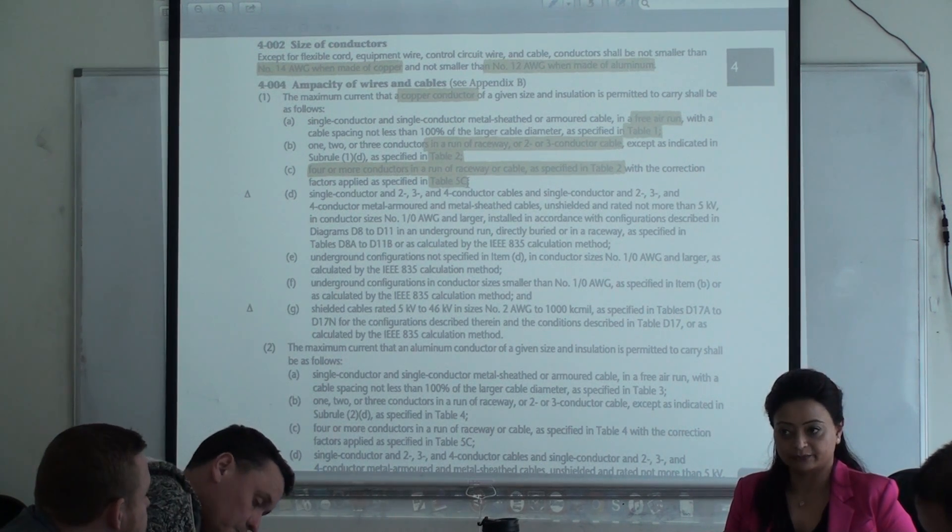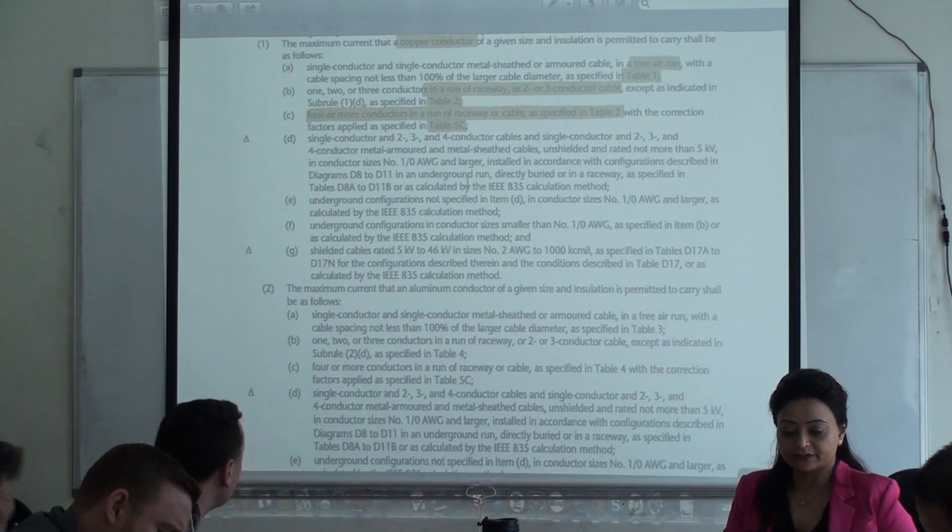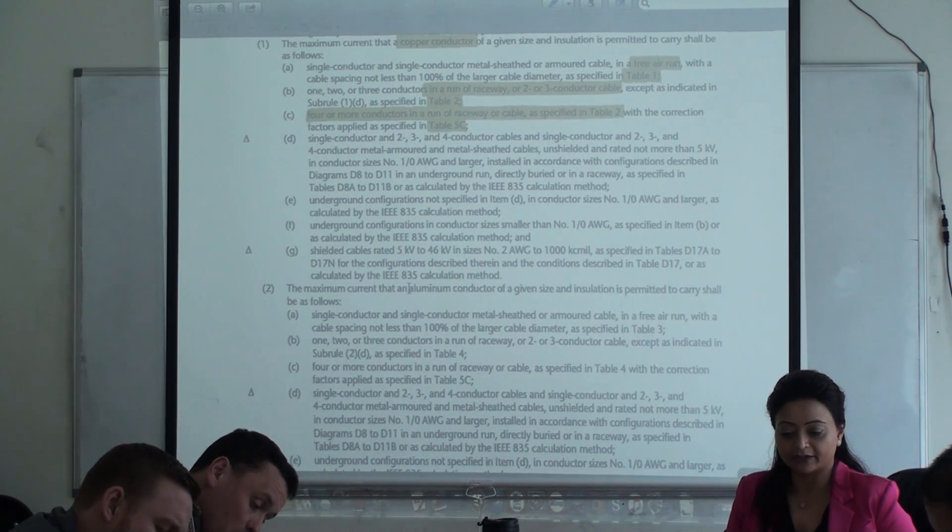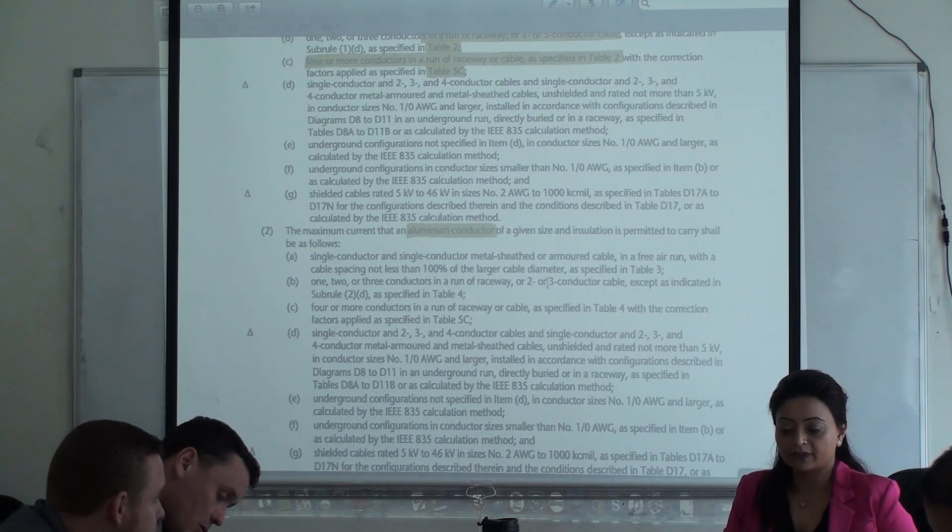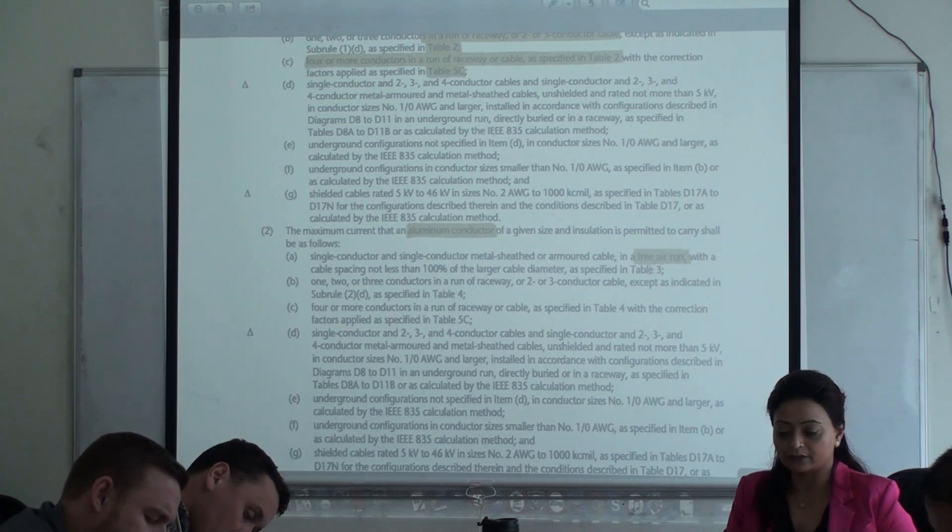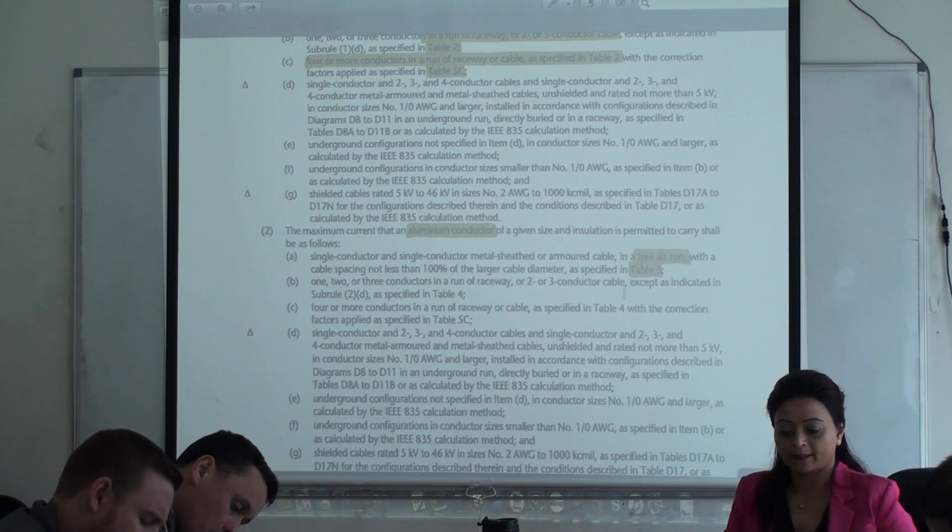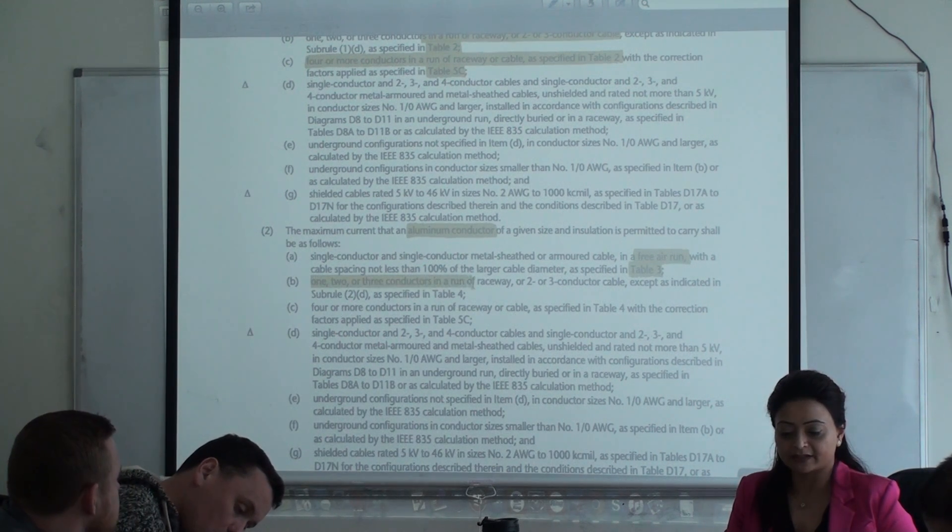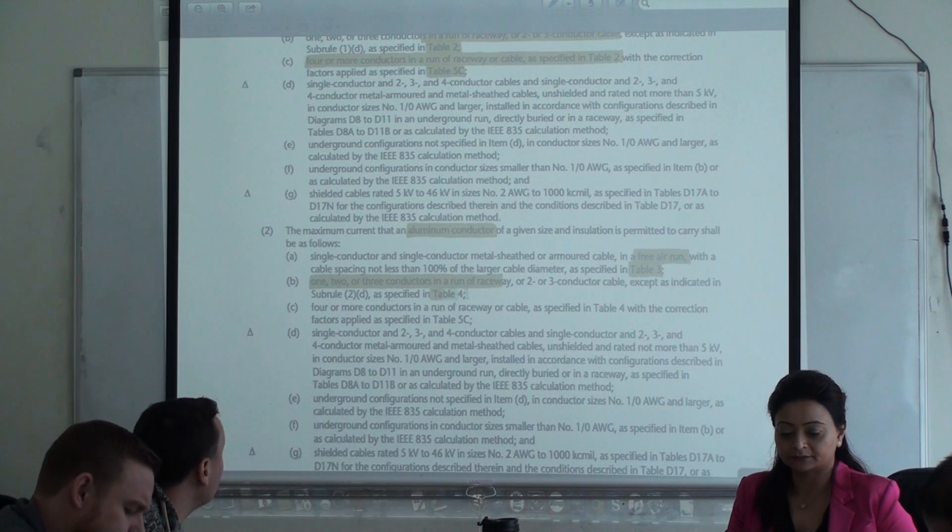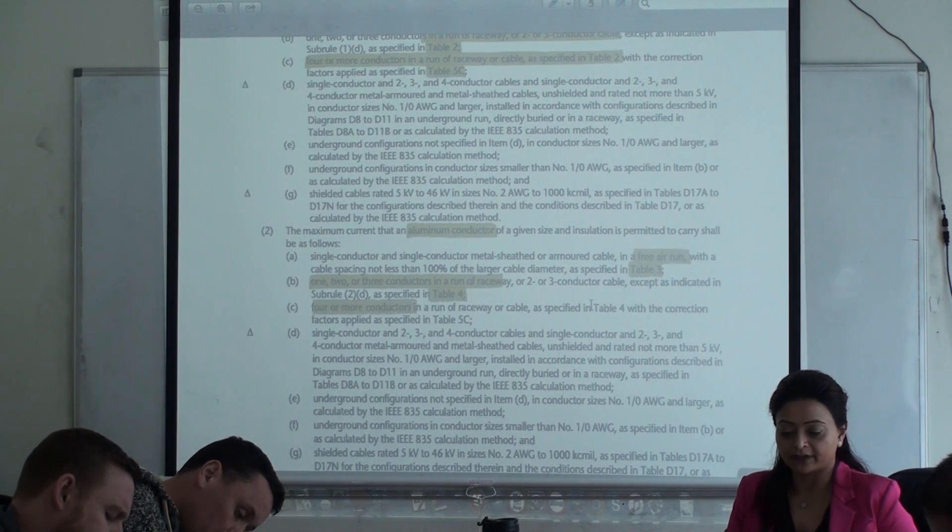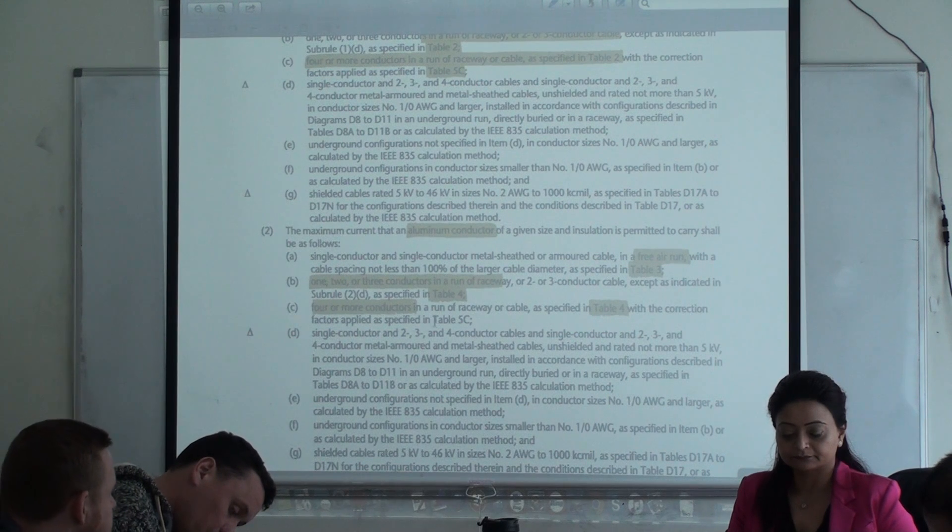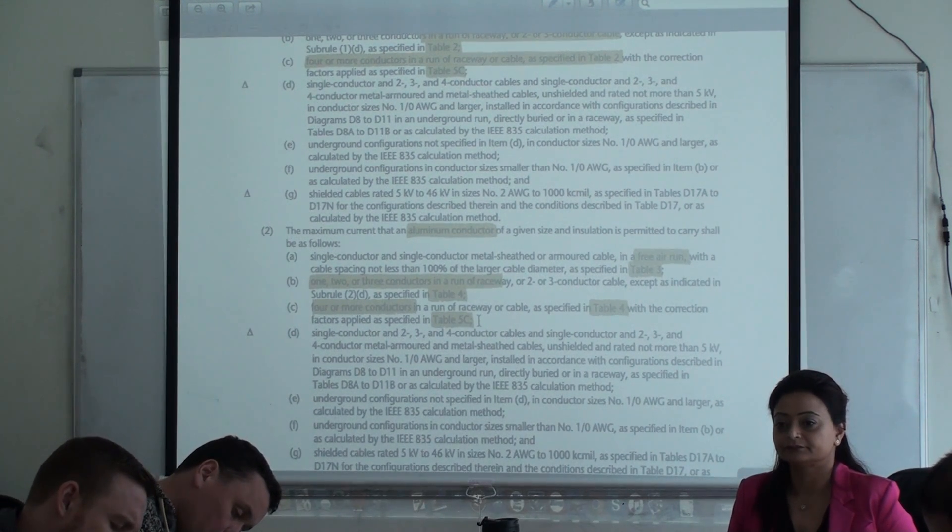Now we're going to talk about aluminum. Aluminum is in sub rule two. In sub rule two, you're going to highlight the word aluminum right here. When aluminum wire is in free air, you go to table three. When you have three wires in a raceway, you go to table four. When you have four or more wires, you go to table four and table 5C. Done.